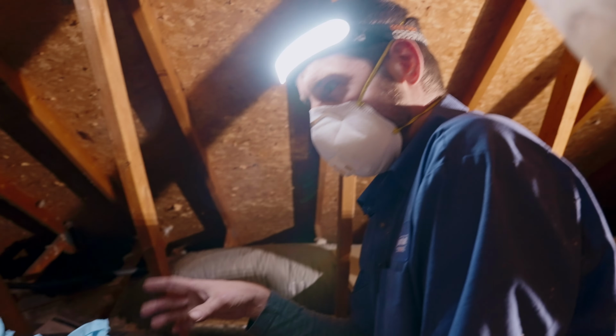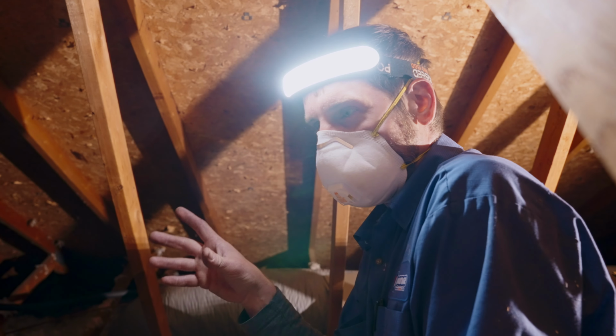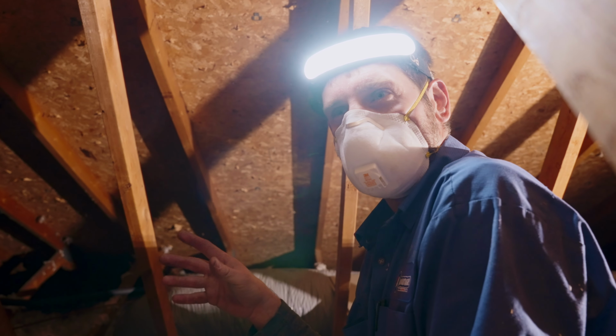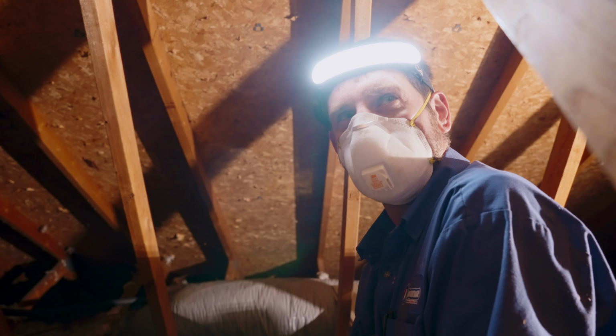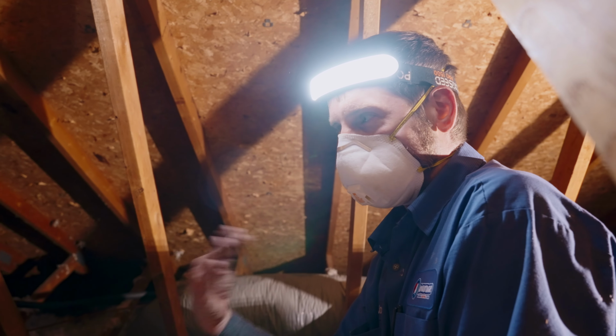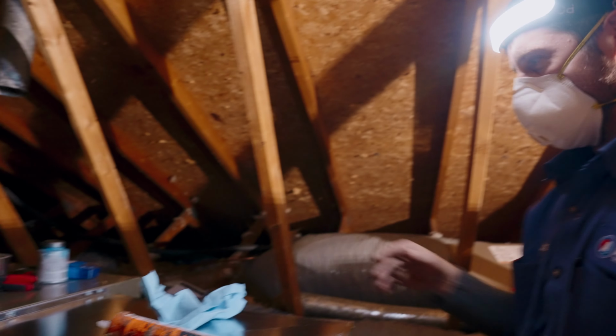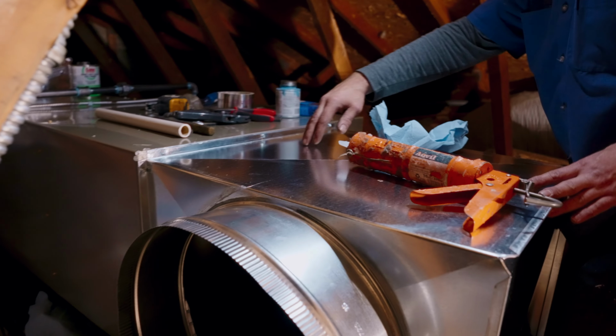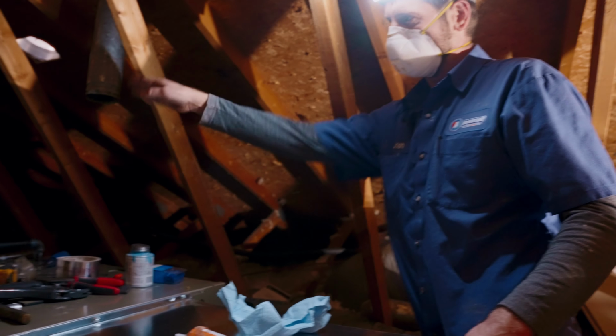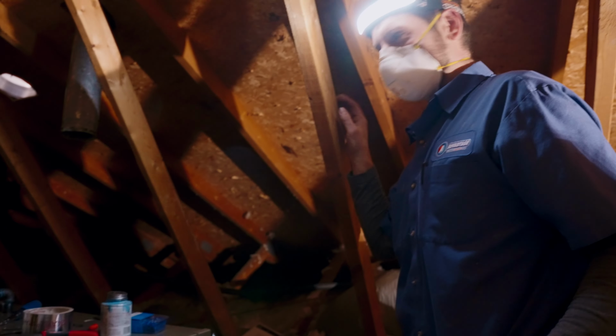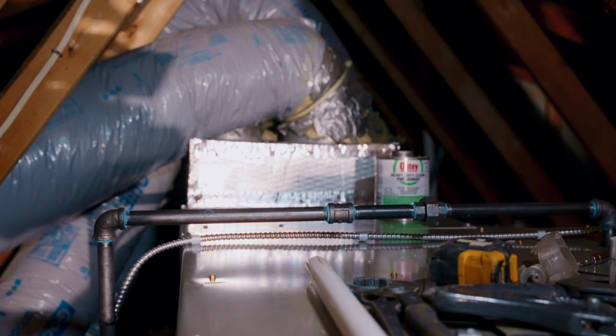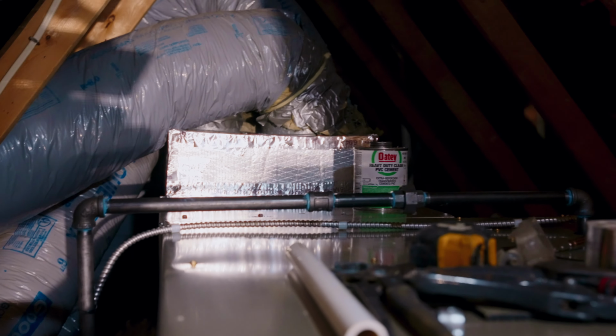So this Bryant furnace, it's a multi-position. It can go as an upflow, like in a basement application. It can go downflow. A lot of slab homes will have a downflow. And then a horizontal right or left. This is a horizontal right. So it's sucking in from here. And this is the front, and it's blowing the air out the top to the right. That's why it's called a horizontal right. And then we got our 2-ton coil up there. They'll blow through there, and we disperse that existing supply plenum there throughout the building.